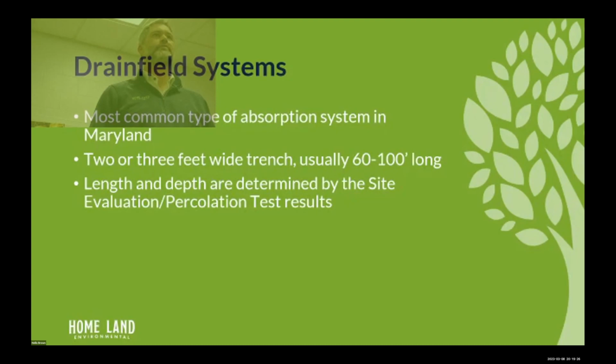Any question? Both. Tanks have to be weight bearing. Drain fields don't. The bigger damage with drain fields, other than breaking the pipe, is compacting the soil and cutting off the oxygen. And that can really take a lot of years off the life of the system.